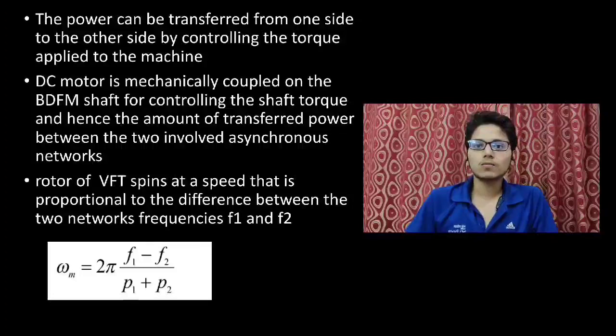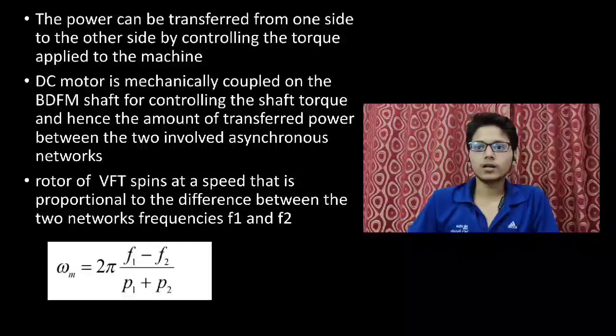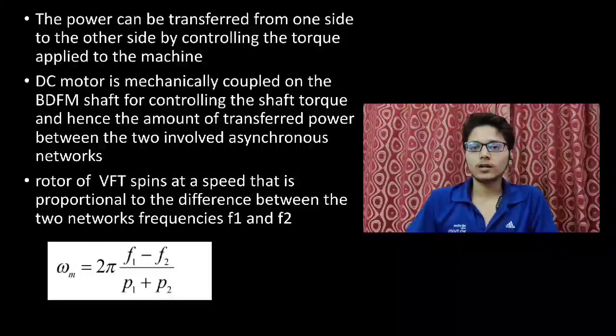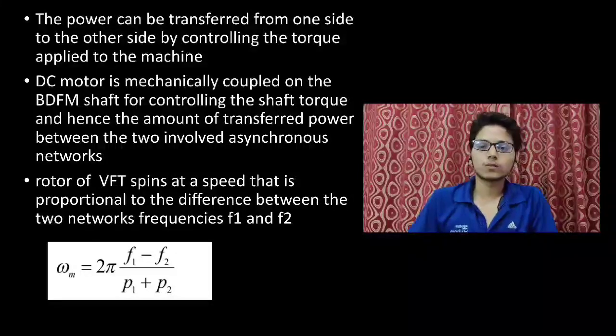Generally, a DC motor is mechanically coupled to the BDFM shaft to control the shaft torque, and hence the amount of power transferred between the two asynchronous networks. The power transfer magnitude and direction depend completely on the torque applied by the DC drive. For example, if the torque is positive, the power will be transferred from the first stator winding to the second stator winding, and vice versa.